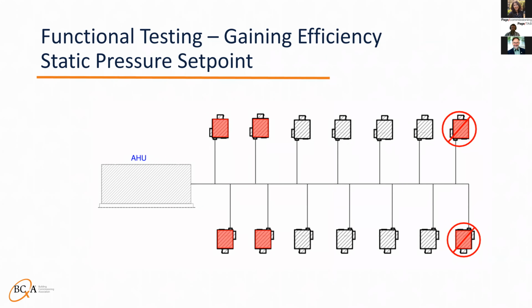Once the system settles out and the AHU is at static pressure set point, look for your worst case damper position. Again, the same requirements apply. If your AHU does not reach static pressure set point, you'll have to look for restrictions on the inlet to the AHU, on the outlet prior to the two-thirds sensor, or possibly speeding up the fan either at the drive or sheave. Either way, it is not normal for the AHU to not be able to reach set point regardless of the mode of operation.